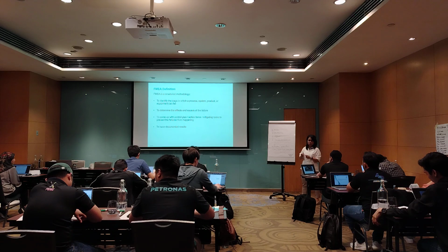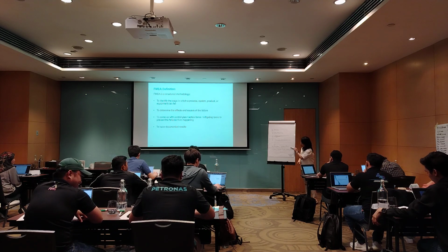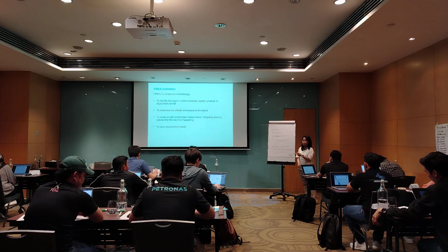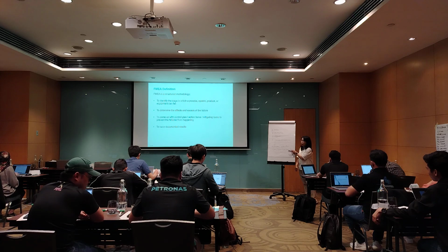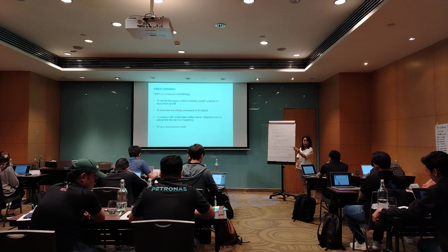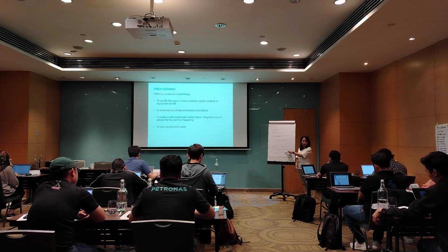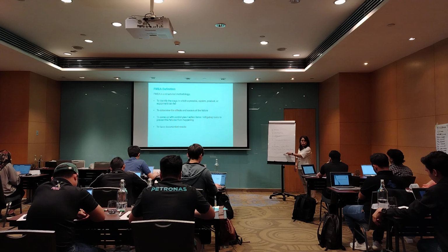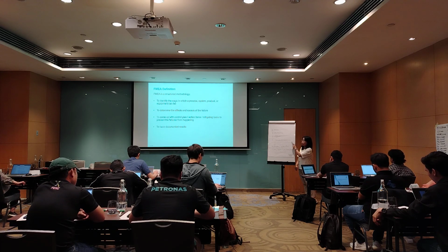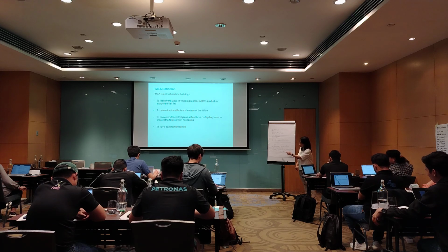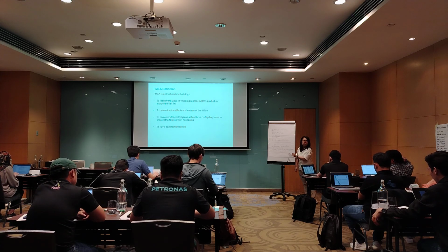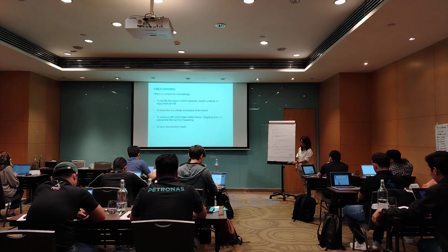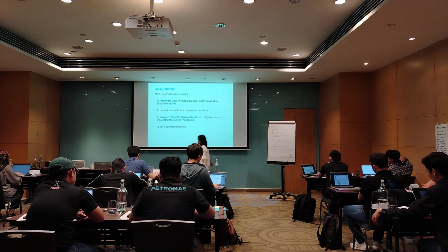These two are missing. When you derive FMEA, nobody will tell you this. Usually people stop here. Then you submit this to the SAP team. SAP asks you back, who to assign this? How frequent do I need to do this? Starting when do I need to do this? Okay, your FMEA process should complete the whole cycle, including who's supposed to do what, and how frequent they need to do it. Alright? This is actually to summarize. Summarized version.